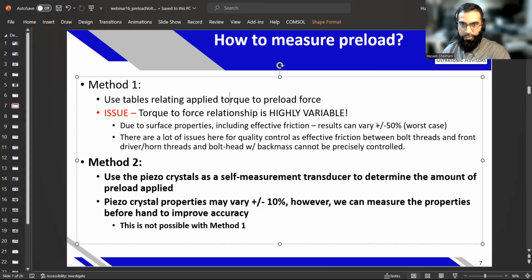The results can vary plus or minus 50% for torque to preload force, but that's the worst case. It can be highly variable. In some cases it could be very consistent, then you'll have an outlier, and that's one product that's not going to work for long term. That can be very problematic. Many of you who have ultrasonic transducer assembly, manufacturing or R&D experience will know that even if you assemble everything as much the same as you can, the results will have a good amount of variability, and that confuses some people. Because the end product will have variability, we need to make sure everything that goes into the transducer is as similar as possible, because we don't have that signal-to-noise ratio at the end of the process to know all the time what's a good and bad transducer. We really rely on assembly processes to ensure quality, because you can't always measure those properties at the end.